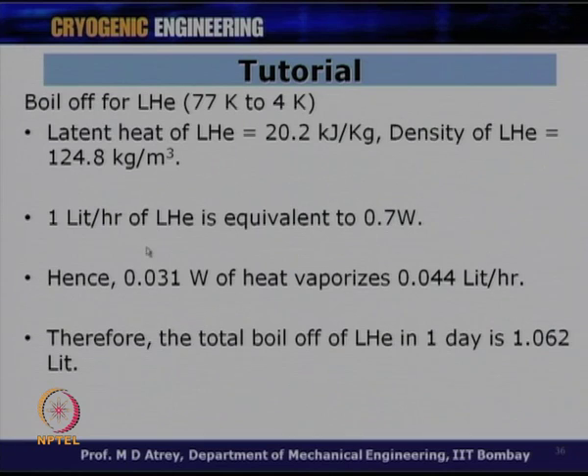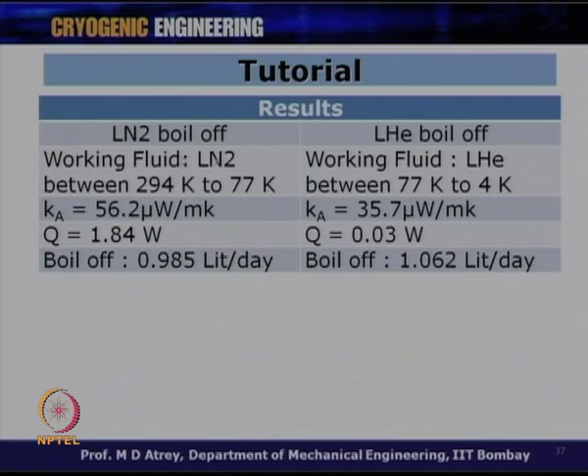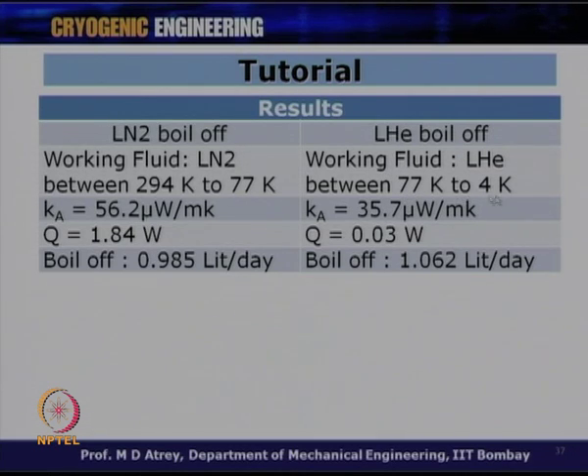Since 0.7 W causes 1 liter/hour LHe boil-off, 0.031 W causes 0.044 liters/hour (44 cc/hour), giving about 1.062 liters per day of liquid helium boil-off. Summary: LN2 boil-off (294–77 K): Ka=56.2 µW/m·K, Q=1.84 W, boil-off≈0.985 L/day. LHe boil-off (77–4 K): Ka=35.7 µW/m·K, Q=0.031 W, boil-off≈1.062 L/day. Both are approximately 1 liter per day.